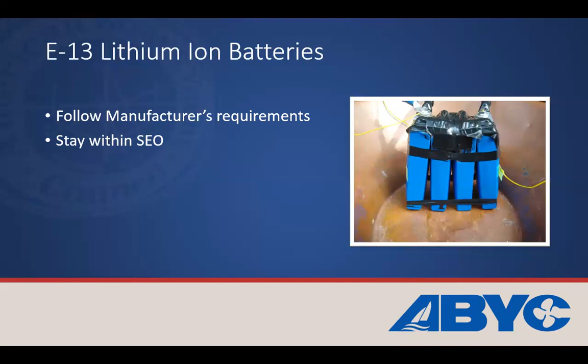You also need to look at the cold side of it as well. Once you start getting below freezing, these batteries don't like to take a charge. They really shouldn't be charged, and the BMS actually cuts that off. So you also need to look at the charging rate, what equipment you have, and make sure you are staying within that, as well as the discharge rate. So I alluded before, you have this thing called a BMS that deals with some of this. All these things can have an impact on the battery.